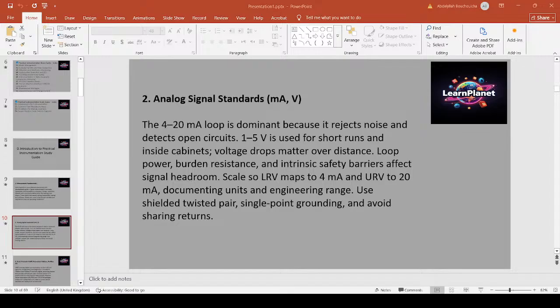The 4 to 20 milliamp signal is preferred in the field because its current loop is immune to voltage drops and allows live detection of open circuits. 0 milliamps is a fault. Voltage signals, for example 0 to 10 volts or 1 to 5, are fine inside the cabinet or on short runs but suffer from cable drop and require attention to input impedance.